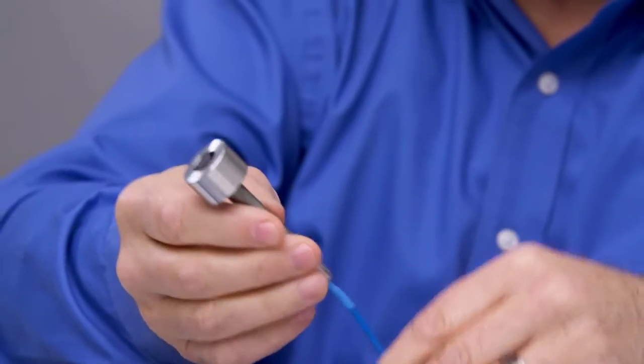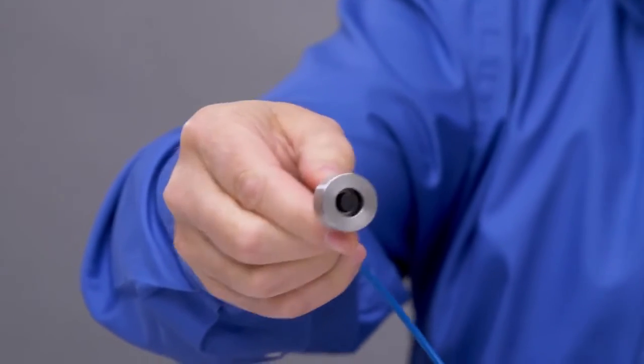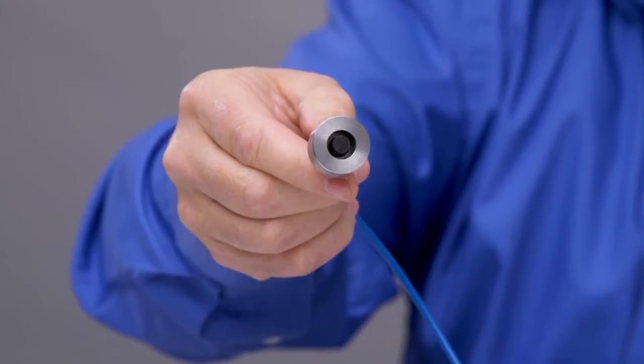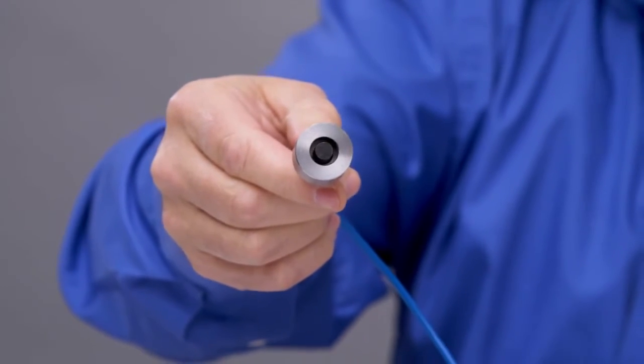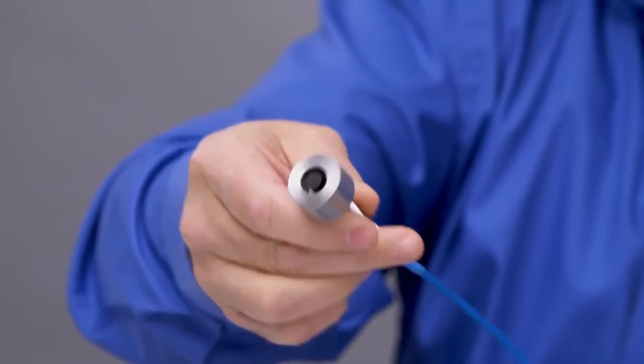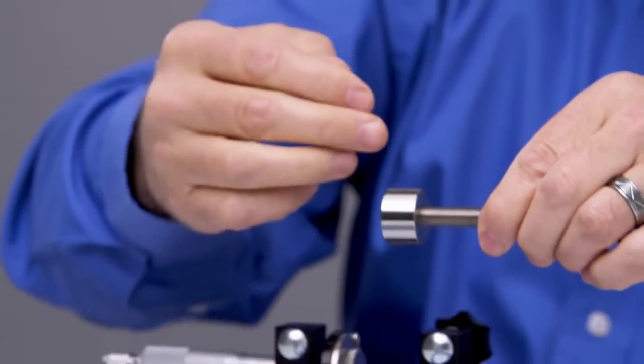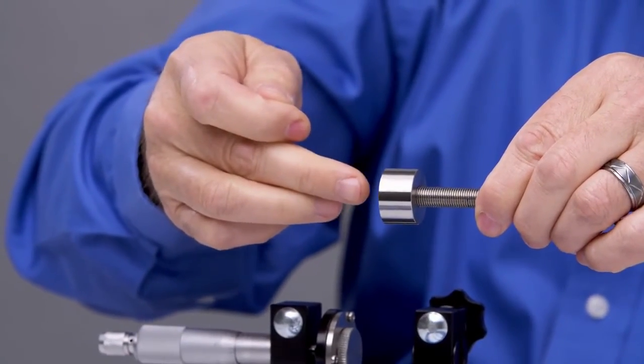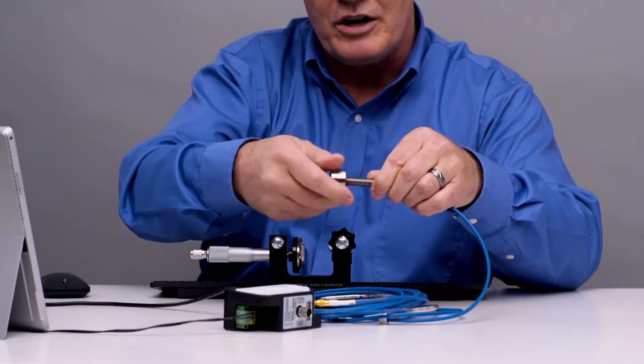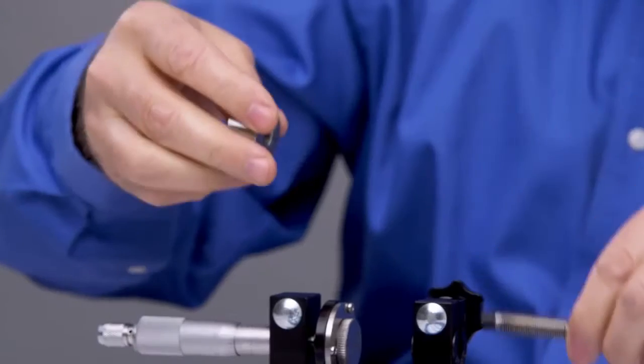What we mean by a tight view, you can see when you look at this fixture that the probe is very close to the metal on the sides, and that's what we mean by tight view. So when I put it in the static calibrator, I'm not only going to have a tight view on the sides, but I'll also be measuring the gap as I move the target away from the probe.